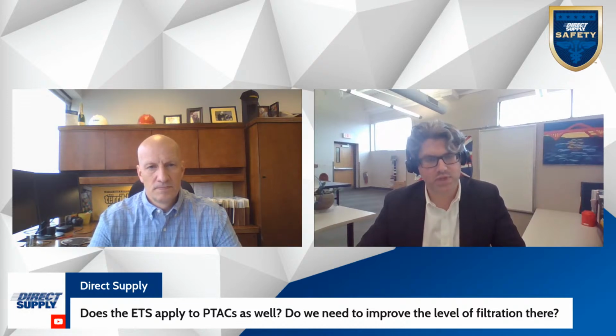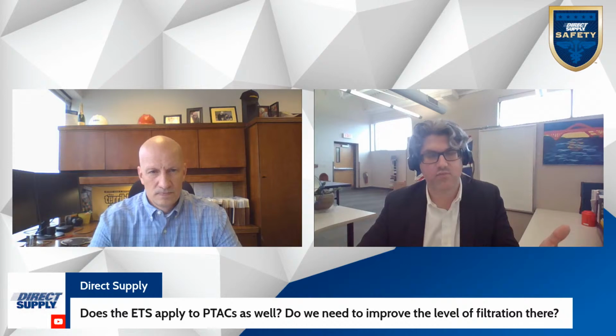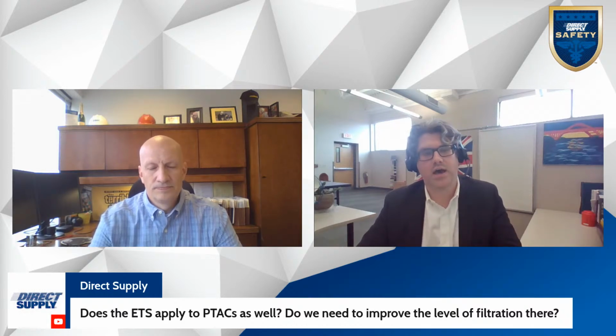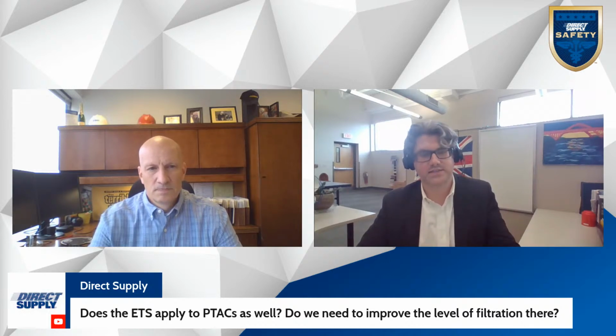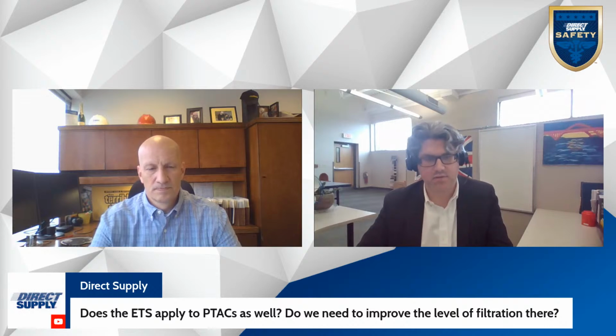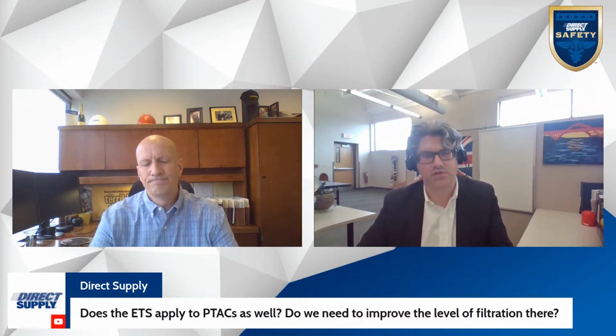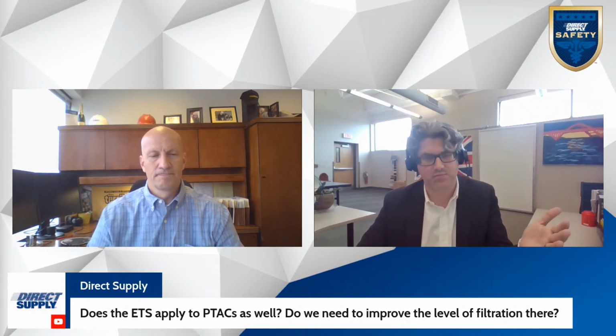My understanding of it would be similar to yours - it probably is considered part of the HVAC system. PTACs very rarely have filters; they usually don't even have MERV ratings. They're really just for dust, reusable and cleanable. My understanding of the OSHA guidance is again to use the highest level of filtration appropriate for that system. In a PTAC, that's probably going to be what's in it already to begin with. You're not going to be upgrading to MERV 13 - there's no such thing.